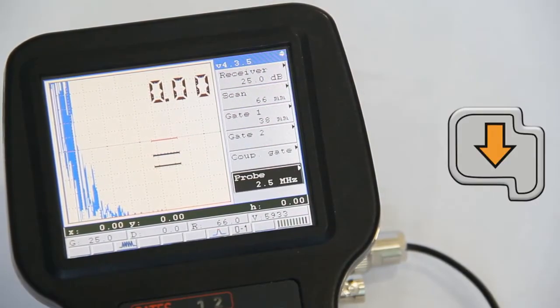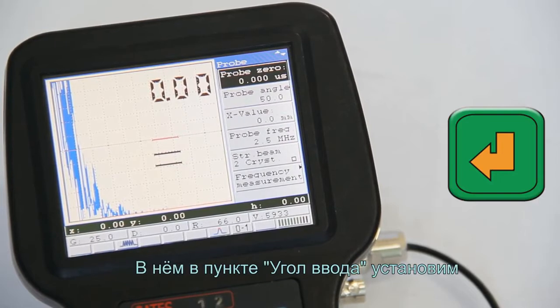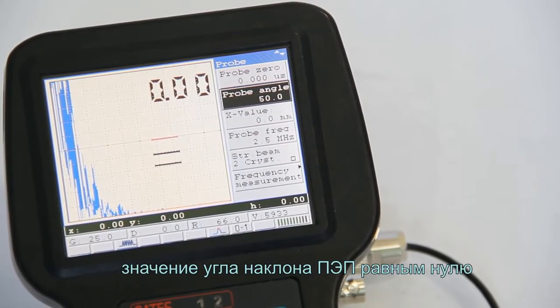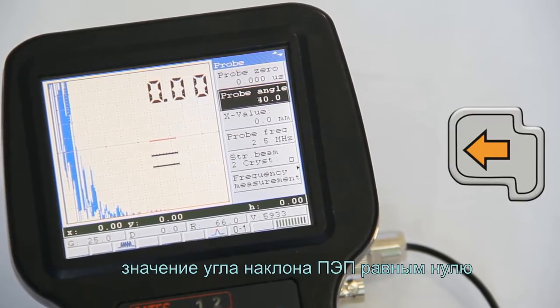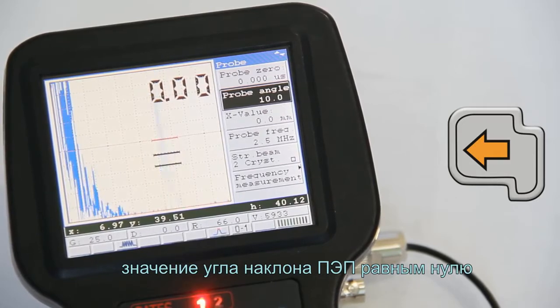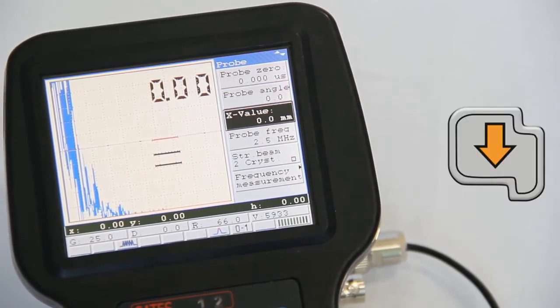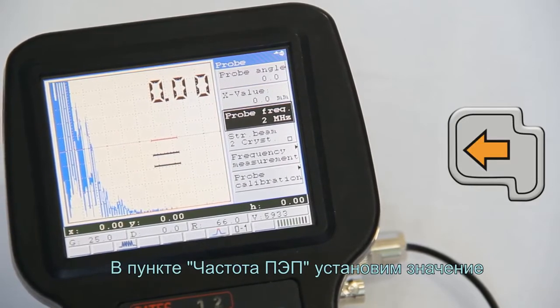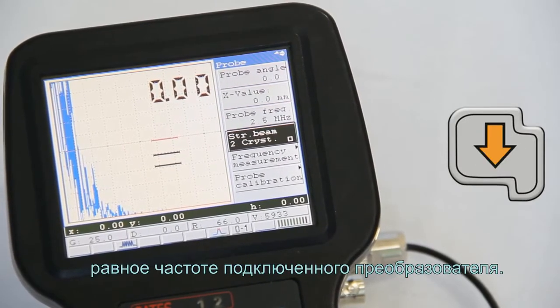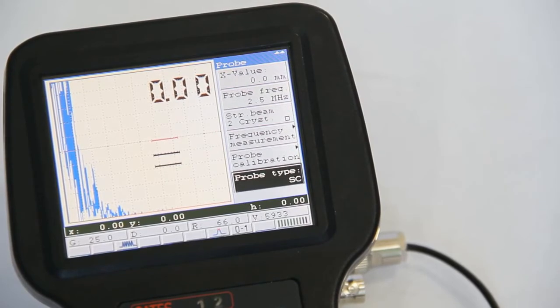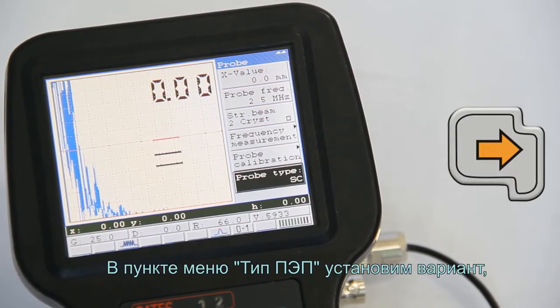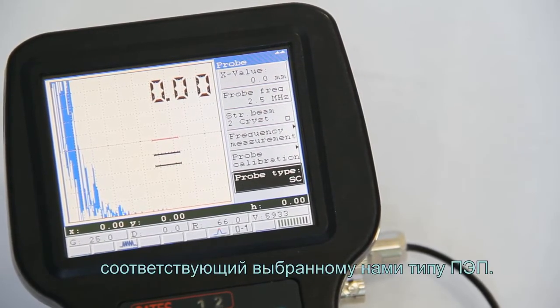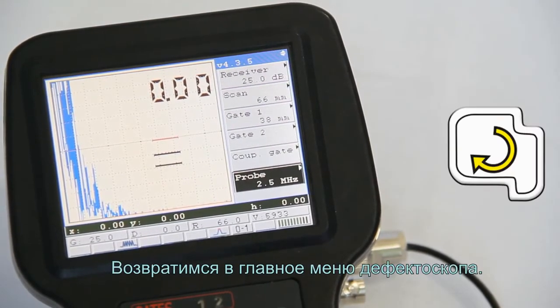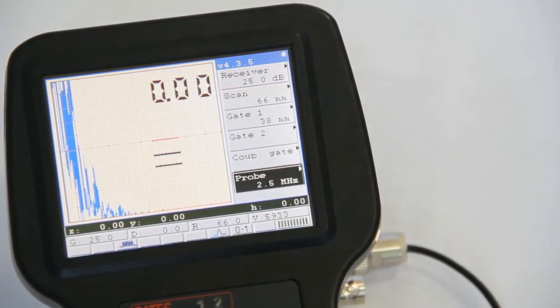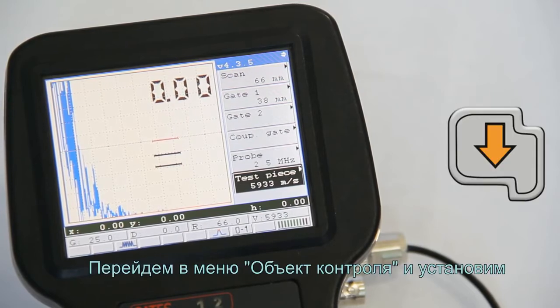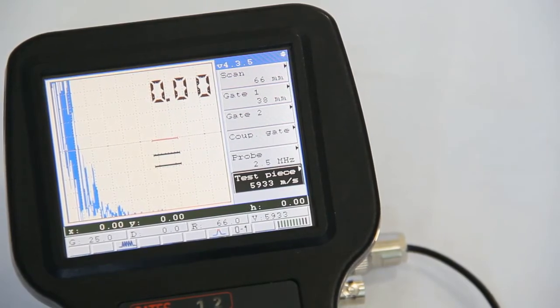Activate the probe menu item. In the probe angle item, set the probe angle value that equals 0. In the probe frequency item, set the value that equals the frequency of the connected probe. In the probe type menu item, set the variant that corresponds to the probe that we have selected. Return to the main menu of the flaw detector. Move to the test piece menu and set the required value for sound velocity in the material.